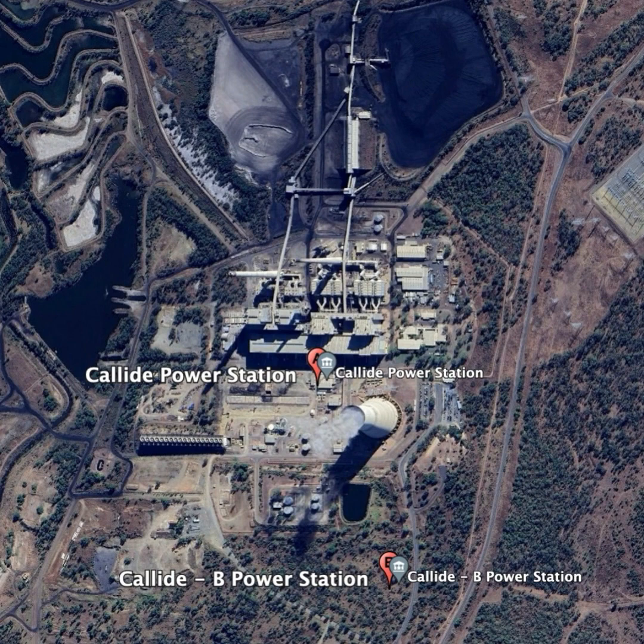On Tuesday, the 25th of May 2021 at 1:28 p.m., the C4 battery string was isolated from the DC charger and remained disconnected from the main DC bus. The station DC bus and the Unit C4 DC bus were both connected via the DC bus interconnector that had been in place whilst the C4 battery string was offline charging on the previous day. At 1:31 p.m., the Callide C4 unit was operating steadily and producing 278 megawatts of power to the Queensland State electricity grid via the Calvale substation.